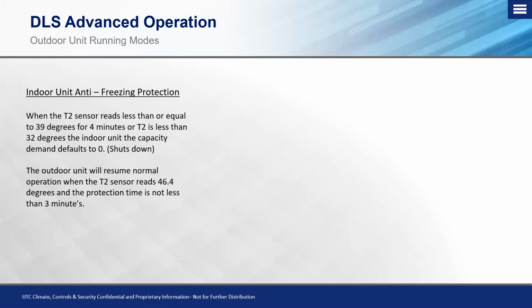Okay. After it shuts down, that outdoor unit will resume normal operation when that T2 sensor reads 46.4. We'll just round it down to 46 degrees. And the protection time is not less than 3 minutes, which we know is the protection time for the compressor once it shuts off. So it's looking for that T2 sensor to read 46 degrees or greater before it restarts after shutting down this particular indoor unit on a temperature sensor code.